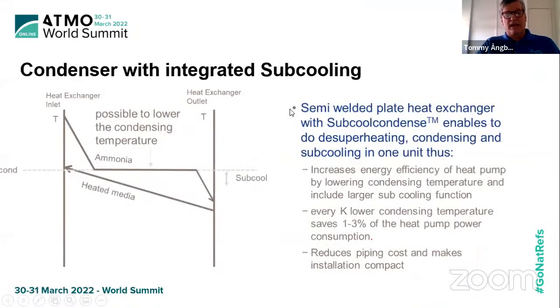And here you can see what can be gained from that. We have the heat exchanger again, and inside it you have the heating media, the desuperheating, the condensing, and the subcooling. In this case, we can lower the condensing temperature closer than ever before was possible. You could get an outlet temperature of the heated media that is about the condensing temperature, at least, maybe even higher, in one heat exchanger. So this is what we call the subcooled condenser.